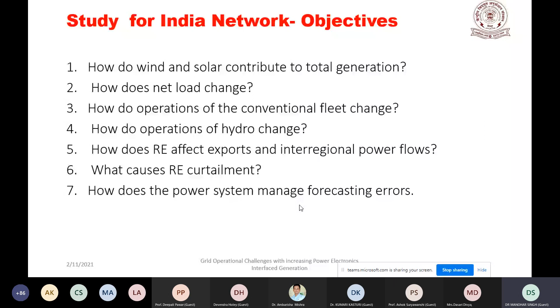Their major observation: power system balancing with 100 gigawatt of solar and 60 gigawatt of wind is achievable at the 15-minute operational time scale with minimum RE curtailment. The 160 gigawatt together can be managed with the present 15-minute operational time scale without much RE curtailment. There is around 2% RE curtailment under certain contingency, but it is possible. The 160 gigawatt of solar and wind will roughly be 22%, as I cited, of the total installed capacity. Presently we are already at 19%. It doesn't mean we are only increasing solar, we are increasing the conventional too. So by 2022 it will be 22% of total installed capacity.